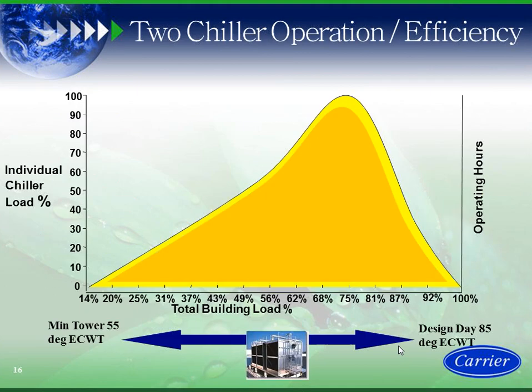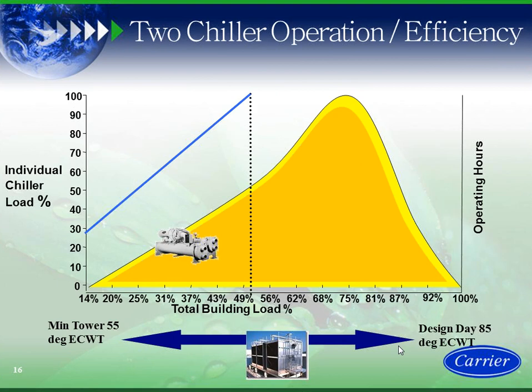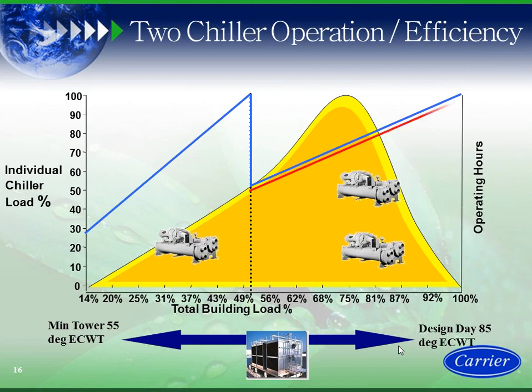So let's look at a 2-chiller plant operation. Again, I have building load on the bottom, and percent chiller load on the side axis. Down at the 14% load point, I have a minimum of 55-degree entering condenser water, and my design day would mean a minimum of around 85-degree entering condenser water temperature. As I load up a typical building to 100%, after I reach my 100% point, I'm then going to turn on 2 chillers, and the 2 chillers will then ramp up from 50% to the 100% point. That's a typical operation of a 2-chiller plant here in the Chicago and Milwaukee area.